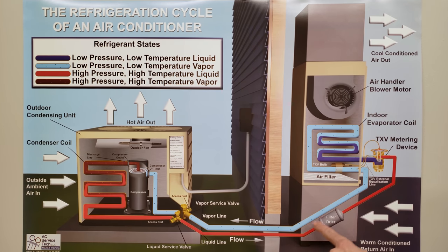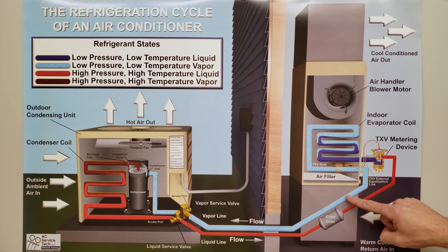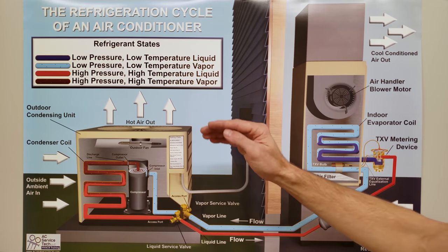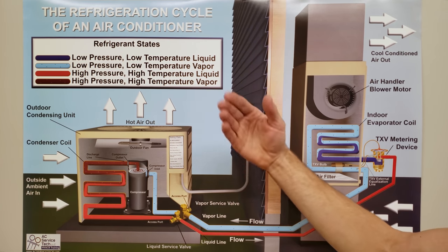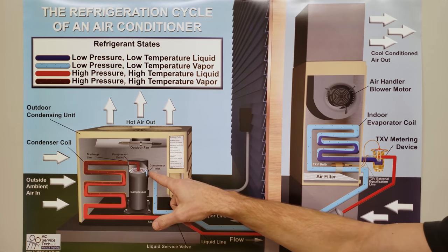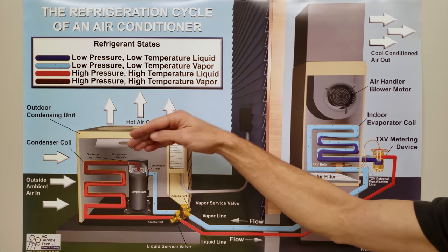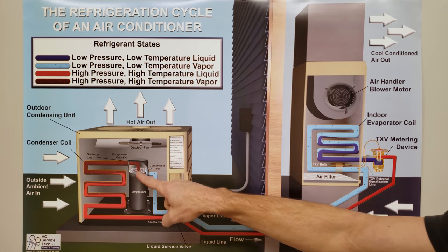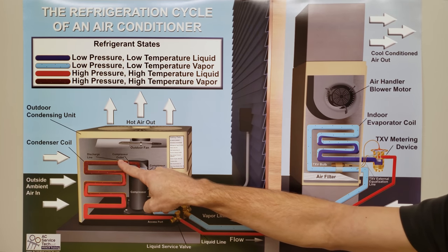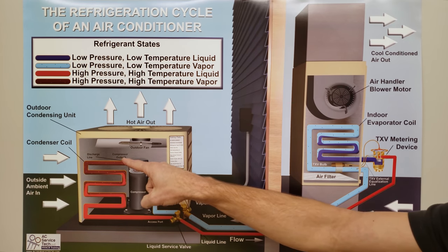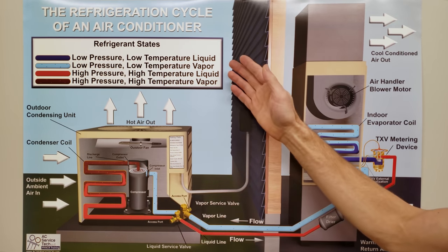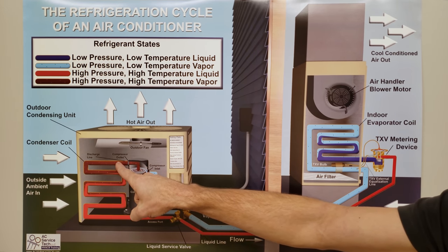The refrigerant vapor carries the absorbed heat energy to the outside in order to reject it to the outdoor air. The problem is if you only have 52°F refrigerant and the outdoor air is 90°F, you can't reject heat into hotter air. So you increase the pressure to increase the refrigerant's temperature. The compressor takes low-pressure vapor in and outputs high-pressure, high-temperature vapor — increasing pressure increases temperature — so refrigerant exiting the compressor might be around 170°F.